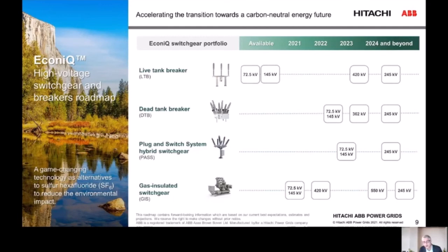Maybe you ask why we do not start by covering sub-transmission everywhere and then go to the high voltage 420. The reason is, as I mentioned before, in 420 kilovolt high voltage gas insulated switchgear GIS, you have a lot of SF6 banked. Today we can replace that with the passive element in about 50%, but still you have 50% in the active element circuit breaker. With this step, we will basically eliminate the whole SF6 in the substation 420, and this is why it has more priority than other products and other voltage levels.